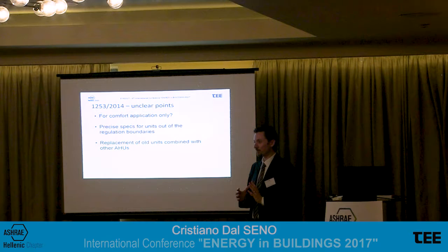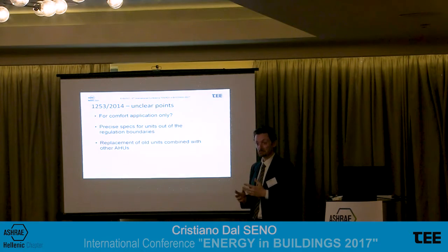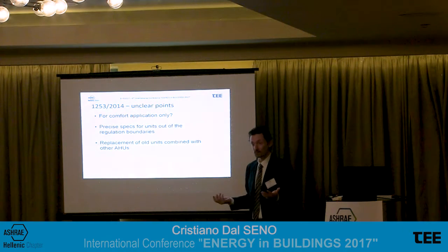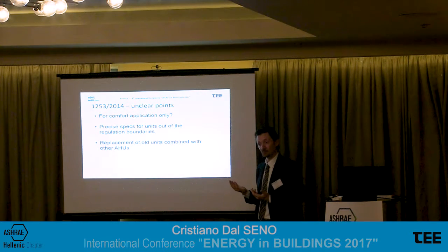Yes, but nowadays with the regulation, I must make it maybe 20 centimeters larger, 20 centimeters higher. In the past perhaps they didn't install the plate heat exchanger, nowadays I must install it, and there's not enough space to place the new air handling unit in the same space where I had the old one. How should we behave? I cannot ask this hotel to dismantle everything and create new ducts to place a new air handling unit somewhere else because in the roof they have not enough space. This point is still unclear.